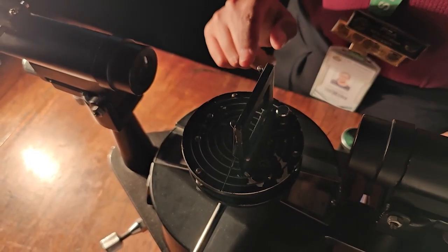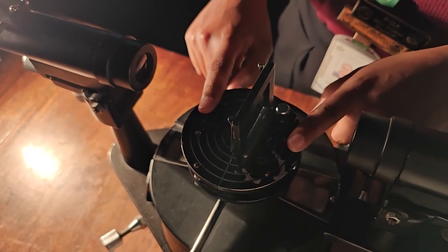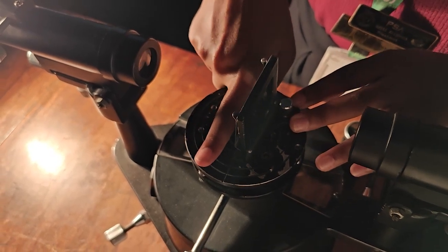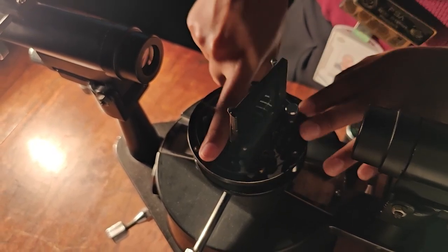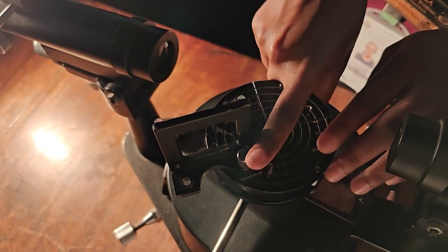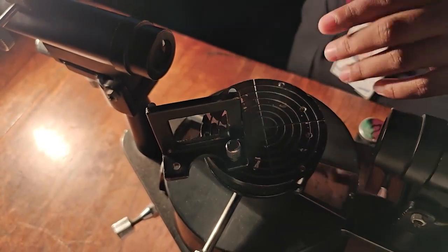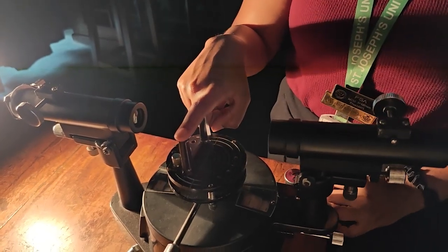Next, use a spirit level to make sure that your grating table is completely flat. So we'll keep it this way. Then we'll keep it parallel to the y-axis and then parallel to the z-axis to make sure that it's perfectly parallel to the table on all sides. Next, we have to add a grating plate over here.